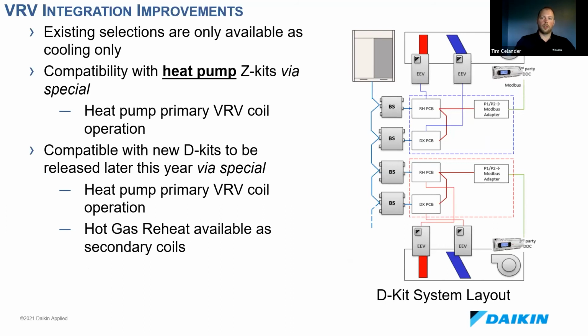And kind of the last new feature that we're offering today is VRV integration. So today we offer a cooling only option that's selectable within our selection software. We now have available heat pump options. So when you get a VRV system, you're getting it not just for cooling your building, you got to heat too. And the coil is going to be capable of doing that. So you can get the Z kits, which will perform heating or cooling in the primary coil in your PreciseLine. Or the VRV groups are going to be rolling out what we call the D kits, which will have that same primary heat pump coil and a hot gas reheat coil. So if you do run into a situation where you're designing for dehumidification, you have that available to you as well.